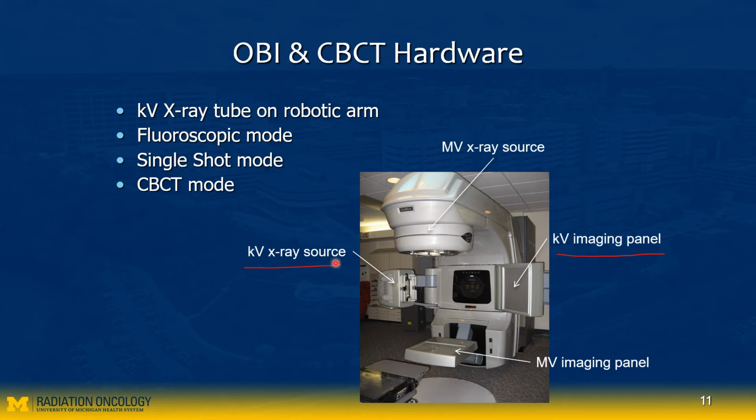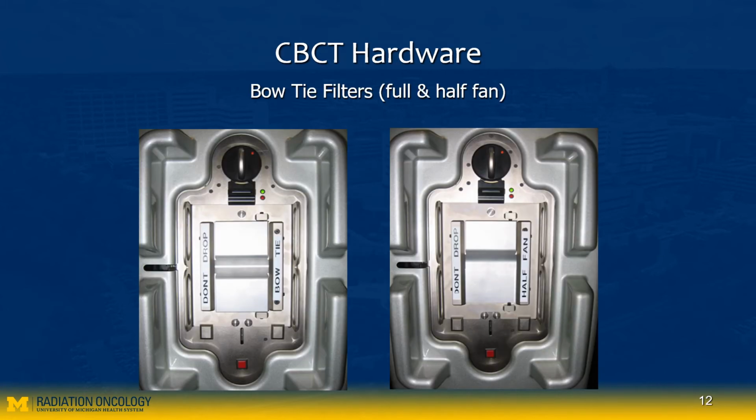So we can use the kilovoltage source and panel not only for CBCT, right? We can acquire a 2D image. It can also be used in fluoroscopic mode.